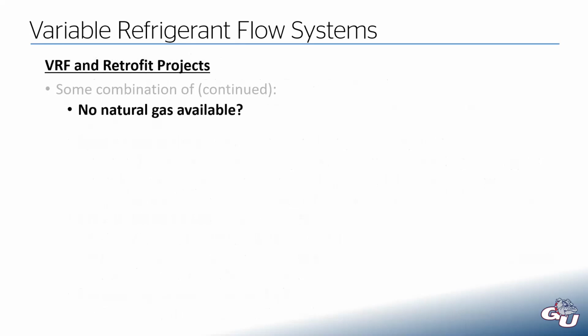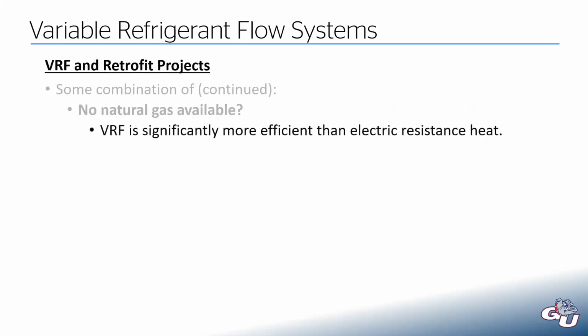You could have a building where they don't even have natural gas, and so VRF is going to be way more efficient than electric resistance heat. And if you don't have natural gas available, really your only options are resistance heat, which is very expensive, or you could have a diesel boiler, which is a giant pain to deal with, because normally diesel boilers aren't connected to a utility. They have a big storage tank buried underground outside, and whenever they get low on diesel, they have to call Joe's diesel store down the road, and they have to come fill it up.